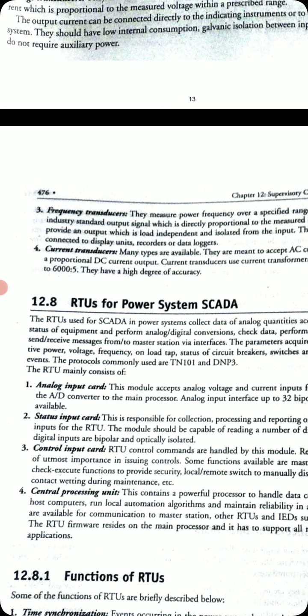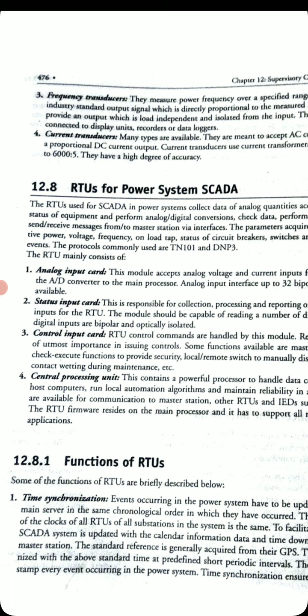Second one is the status input card. This is responsible for the collection, processing and reporting of the various types of contact input for the RTU. The module should be capable of reading a number of discrete digital inputs. All digital inputs are bipolar and optically isolated. Next, the third one is the control input card. RTU control commands are handled by this module. Reliability and security are of utmost importance in issuing the controls.